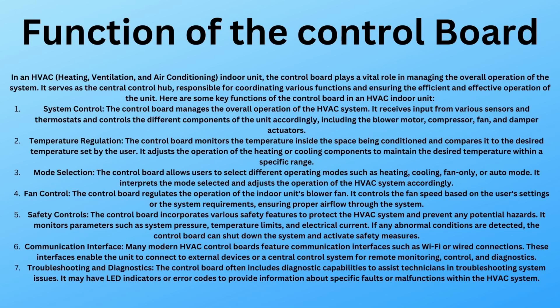It can troubleshoot and diagnose. Back in my day, we had what's called a Thunder Tiger or a Tiger, where I could actually plug into the control board, especially on air handlers that are heat pumps, and I could actually manually make the system do individual things on an individual basis. I can make it hit the gas valve and make the burners work. I can make it hit the blower wheel, make it ramp up. I could test each individual system at the time. Nowadays, it's a little different. They got plugins for your computer, for your laptop. You can plug into it, and it'll spit back information at you on what's going on and how to fix it really quick. It actually makes it a lot easier for the service tech to be able to service and repair the equipment, and for the homeowner.